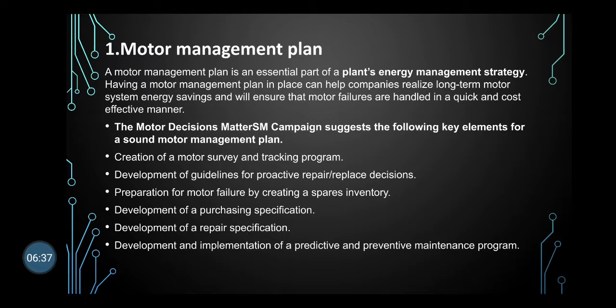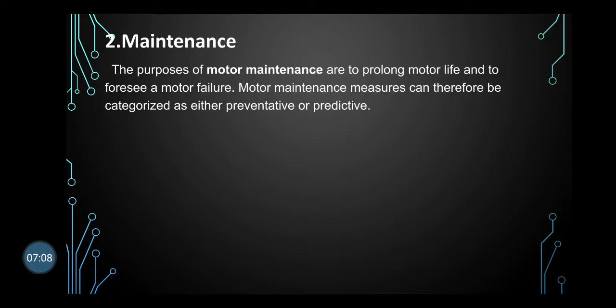Now, second one is maintenance. As we know, the purpose of maintenance is to reduce the losses. This is the main purpose of maintenance. The purposes of maintenance are to prolong motor life and to foresee motor failure. The motor maintenance measures can therefore be categorized as preventive or predictive maintenance. The purpose of predictive motor maintenance is to observe ongoing motor temperature, vibration, and other operating data to identify when it becomes necessary to overhaul or replace the motor before failure occurs.